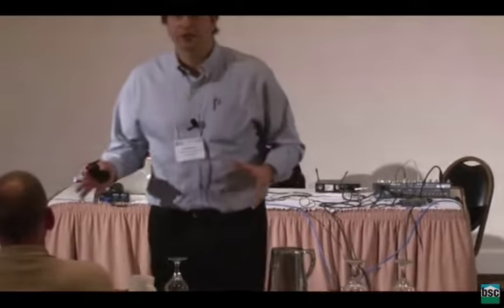It is actually the ideal solution. So I know there's a manufacturer in Ontario who's working on a cold climate heat pump model, and they're putting all their compressors indoors, and it makes a significant difference under heating mode. Under air conditioning mode, of course, it's less effective, but if you have more heating to worry about than cooling, then it would make sense to do it that way. If you're in Houston, you're going to put the compressor outdoors because you're mostly cooling rather than heating. Pretty straightforward stuff. But anyways, we just haven't had a lot of options available to us.